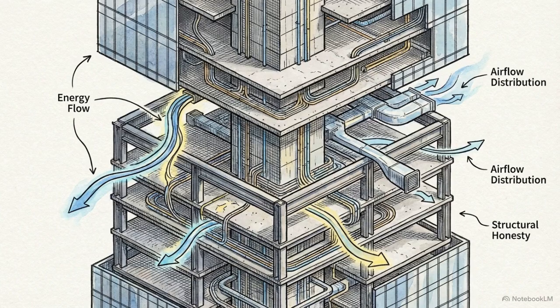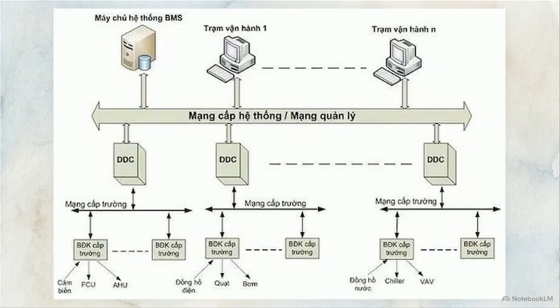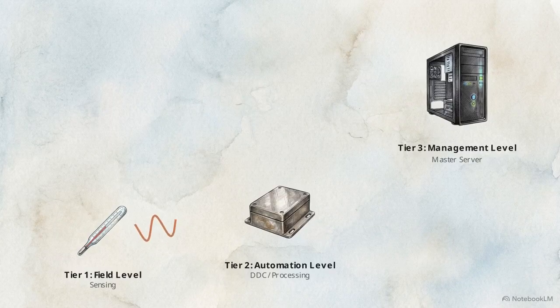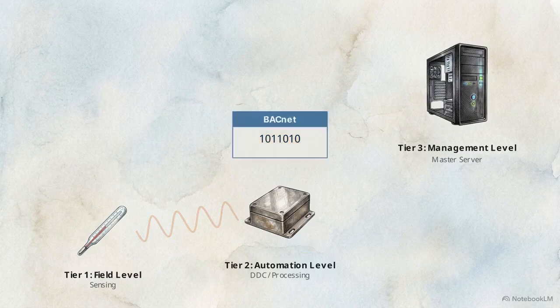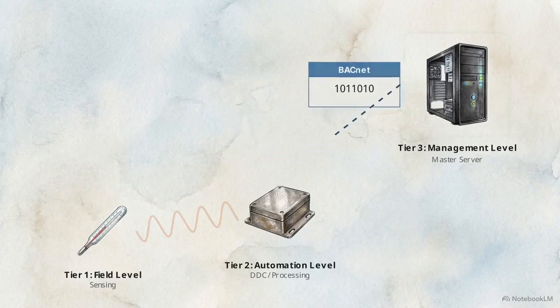We can trace this entire automated sequence from the bottom up. A Tier 1 temperature sensor detects a sudden heat spike in a conference room. It sends an analog signal to the Tier 2 DDC, which digitizes the reading, wraps it into a standardized BACnet packet, and pushes it up to the Tier 3 server.